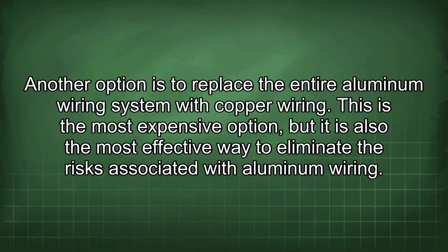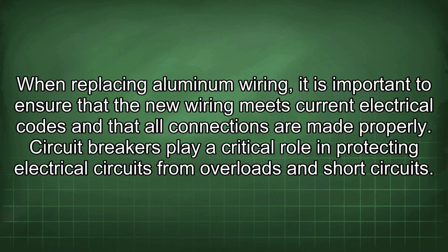Another option is to replace the entire aluminum wiring system with copper wiring. This is the most expensive option, but it is also the most effective way to eliminate the risks associated with aluminum wiring. When replacing aluminum wiring, it is important to ensure that the new wiring meets current electrical codes and that all connections are made properly.